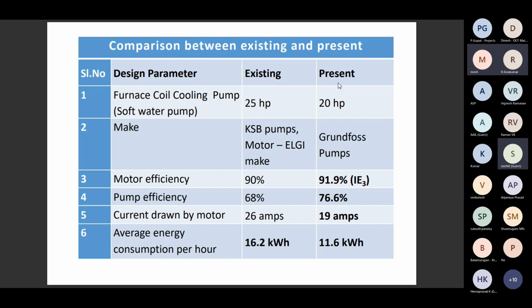The current drawn by the motor is 26 amps. This was taken through our energy analyzing equipment. The new pump was consuming only 19 amps. So the average energy consumption is 16.2 for the old one. The new pump takes only 11.6 kilowatt.